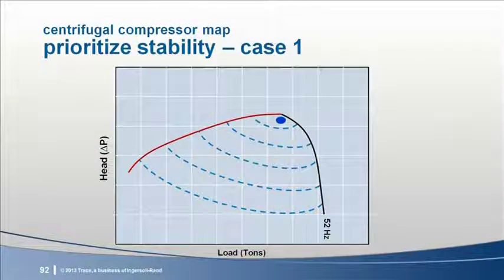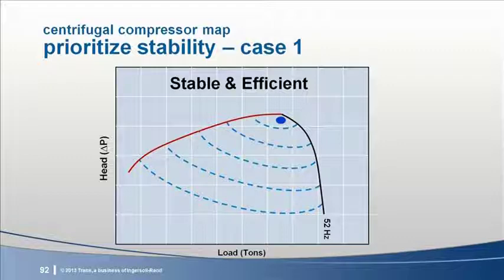Here we see the compressor operating at part load and part lift. The blue dot represents the chiller's operating point as dictated by the system load and the condenser water conditions. The chiller control reduces the compressor's speed to match the system's load and lift requirements as efficiently as possible. Under some conditions, the controls might have to additionally adjust the inlet guide vane position to perfectly match the load, but we'll ignore that for now. At this load point, the control is causing the chiller to operate stably and efficiently at about 52 Hertz or 87% of design speed.